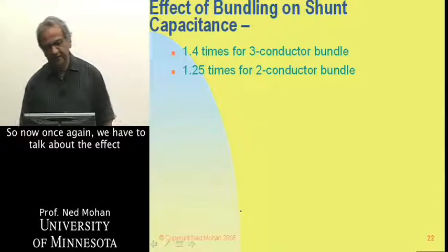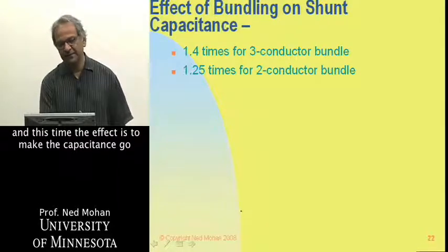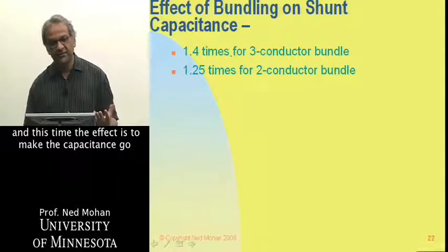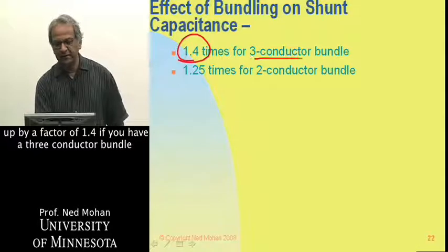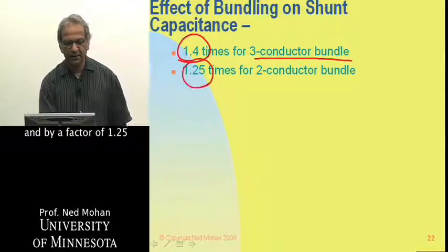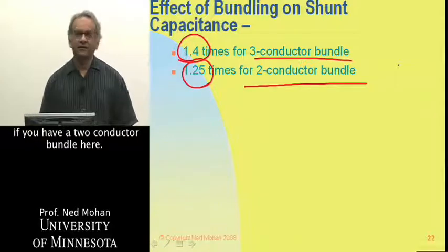So once again, we have to talk about the effect on these shunt capacitances due to bundling, and this time the effect is to make these capacitance go up. By a factor of 1.4 if you have a three-conductor bundle, and by a factor of 1.25 if you have a two-conductor bundle here.